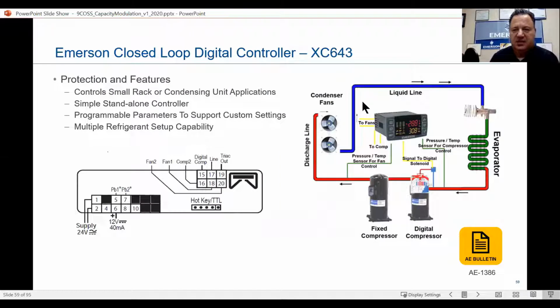Now, this is just that smaller controller. This is what we referred to earlier as the closed loop. The Emerson closed loop digital controller, the XC643. The protection and features: it controls small rack or condensing unit applications, normally no more than 2 compressors or 2 fans. It's a simple standalone controller, with programmable parameters to support custom settings, and multiple refrigerant setup capability.